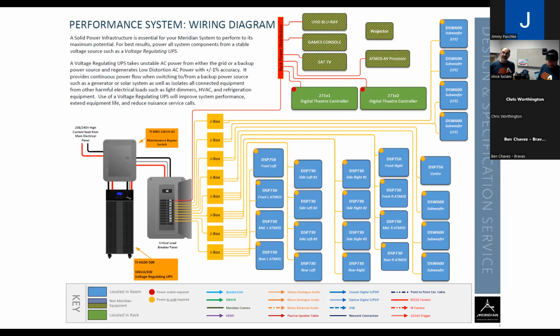The large format UPSs do have an internal bypass, which allows a technician to throw a switch, bypass it internally, and safely work on all the PC boards inside the unit. But in the event the unit needs to be taken out completely, that's where the external maintenance bypass switch comes in handy.